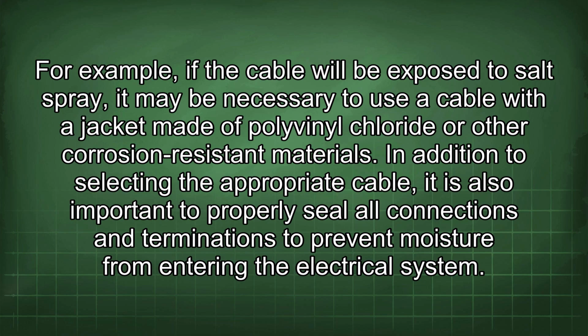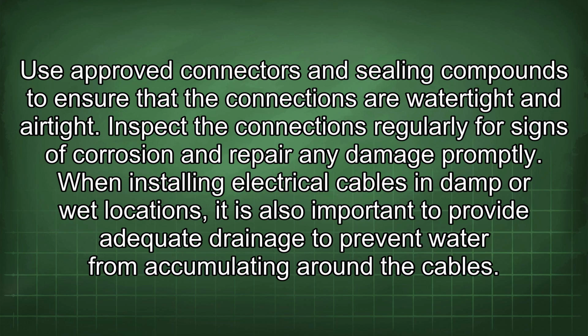In addition to selecting the appropriate cable, it is also important to properly seal all connections and terminations to prevent moisture from entering the electrical system. Use approved connectors and sealing compounds to ensure that the connections are watertight and airtight. Inspect the connections regularly for signs of corrosion and repair any damage promptly.